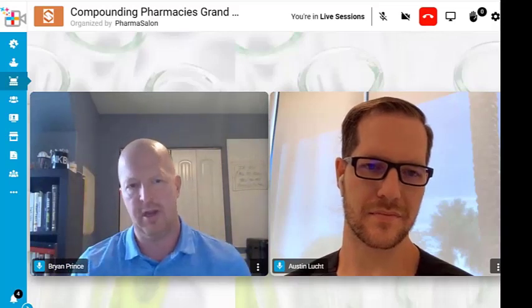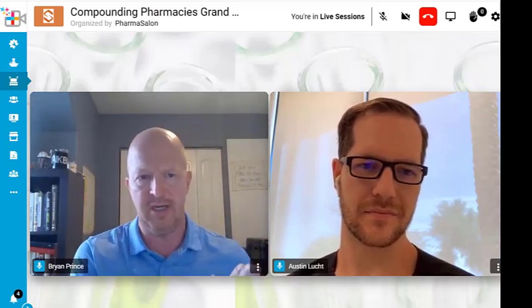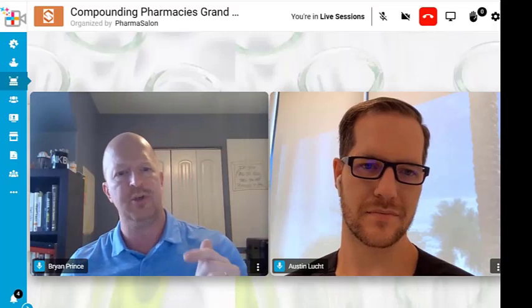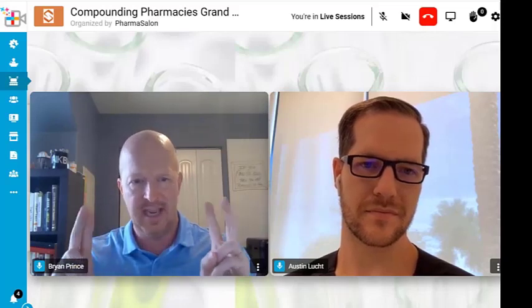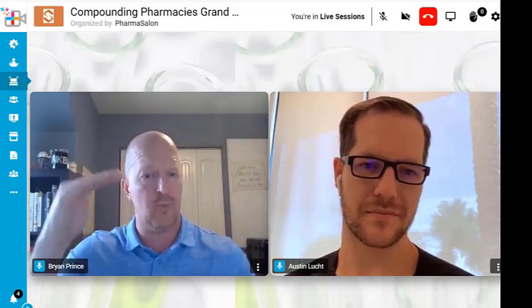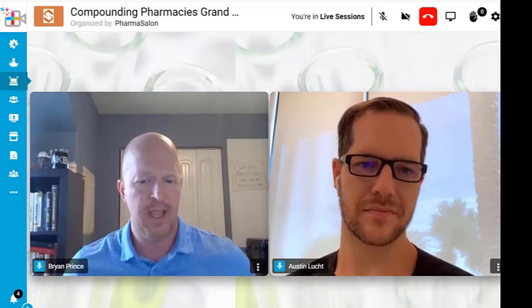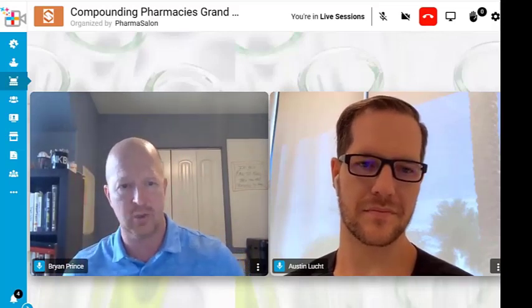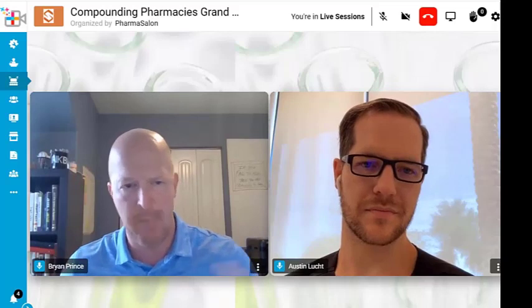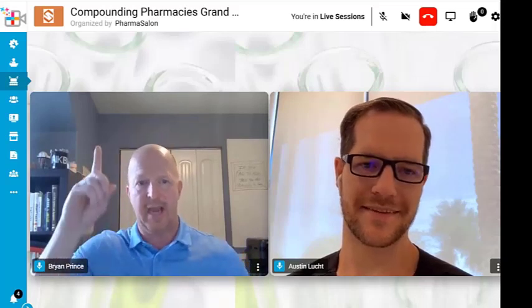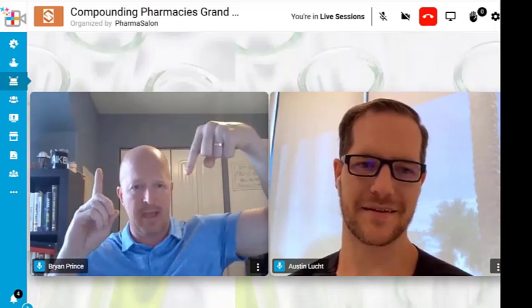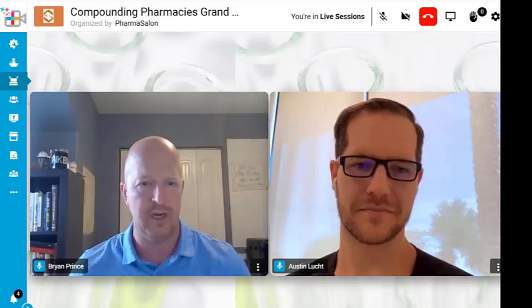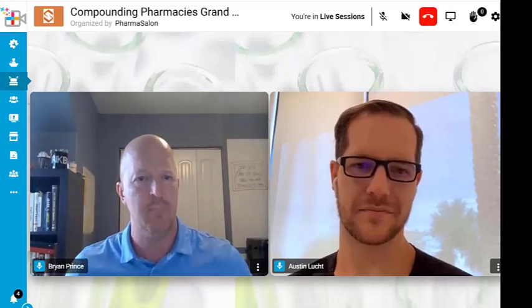So you want to make sure that not only do you spec that temperature and humidity standard that we just discussed, but you also want to put the CFM, which is air, at least 45 air changes per hour. And then also account for all the air that's going out of the building. And if I haven't said it a million times before, if you send air out of a building, you've got to put that same amount of air back in the building. It is a one-to-one ratio, or you're going to have even bigger problems.